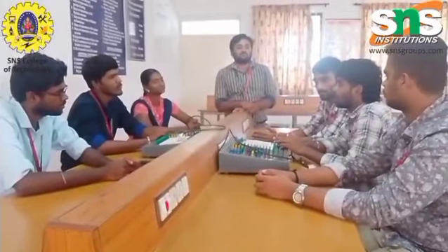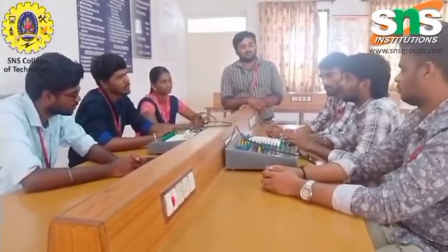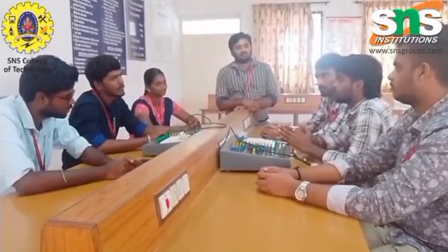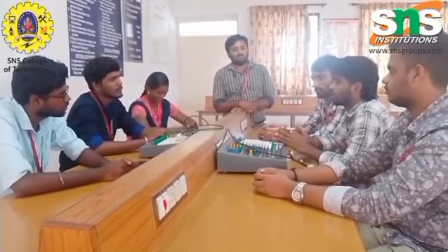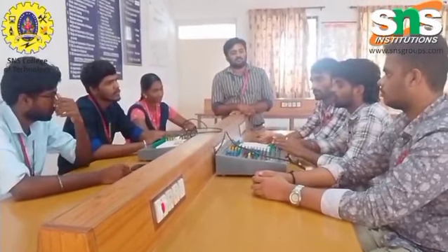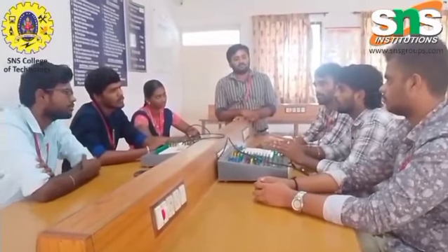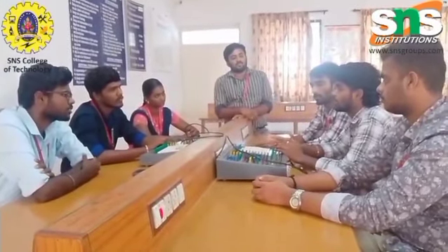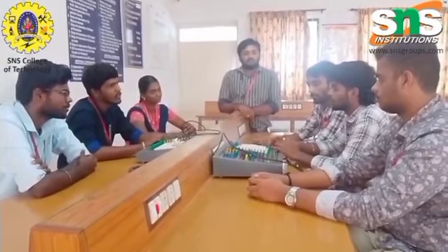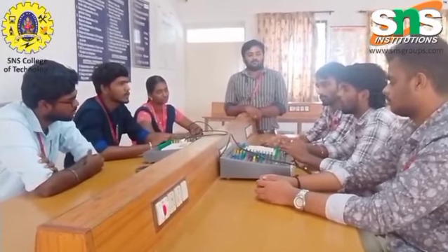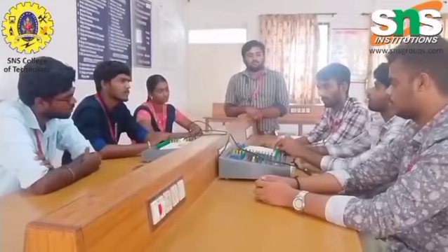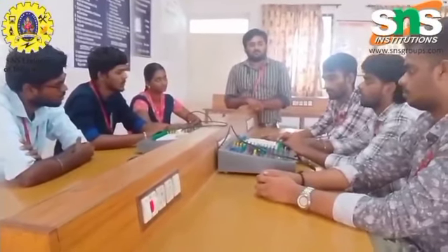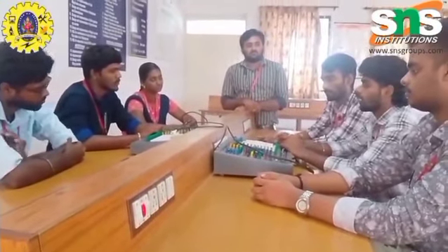Next, applying it to a simulated ECG signal. First of all, simulating an ECG signal: use a function generator to generate an ECG waveform. Many function generators have a built-in ECG waveform function or allow custom waveform programming. Next, real ECG devices.